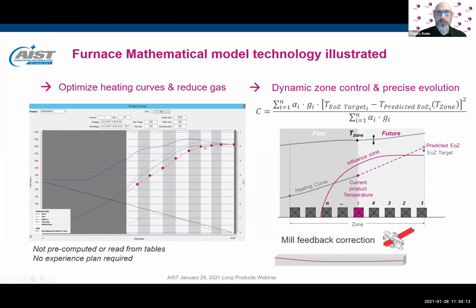So this is completely calculated in real time for all the products. When you know how to heat up the products, you have to control the zones, and you do that dynamically. According to the end of zone target, you predict what the zone will be at the end of it. For each product, take this example here, you know its current temperature. According to the influence, you predict the future zone temperature evolution according to what you're targeting in terms of product temperature. So the aim of dynamic control is to manage all the zones to heat up all the products according to the end of zones, to make sure you achieve all the requirements.